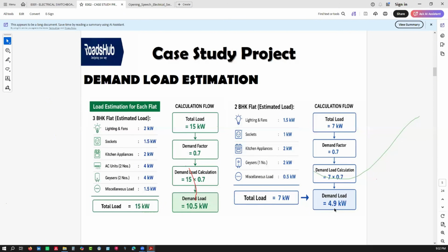The demand factor value, based on the question, you get it from your standards. If you want to calculate yourself based on your environment, you can do that because it's just an equation: demand factor equals maximum load over connected loads. But for that, you need specific loads. Sometimes if you go into your BS standards or building codes used for electrical, you'll get all the demand factors for different loads there.